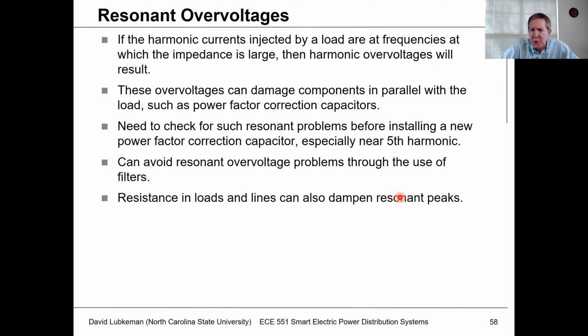Where this is normally a problem is when I put in power factor correction capacitors, essentially near the fifth harmonic. This is typically where we tend to have issues. So it's around 300 hertz or so. And if we hit this resonant condition, then we have to do something about it. Usually we can detune the circuit to make sure that this isn't going to be an issue. But anytime that capacitor would switch in with a harmonic source that had 300 hertz components, that might cause some overvoltages that would maybe blow a fuse, let's say.